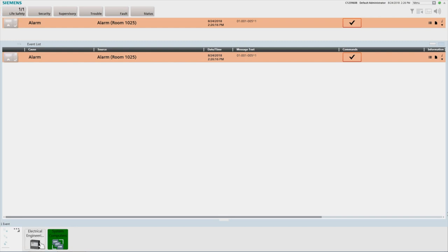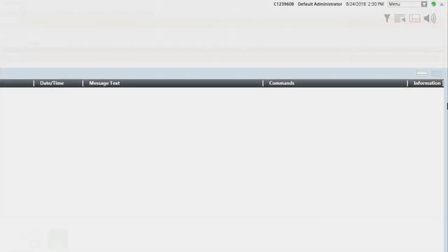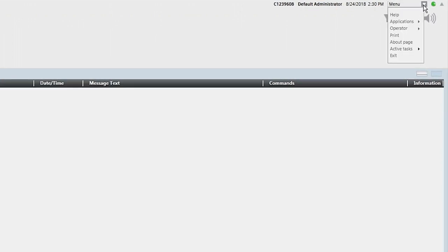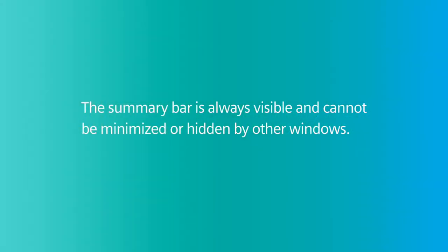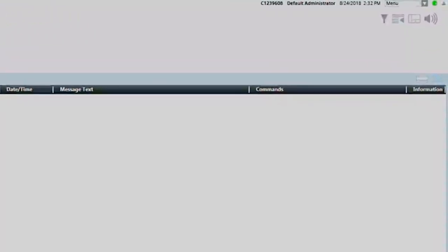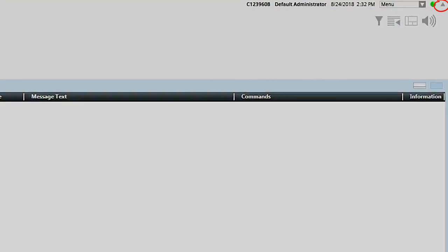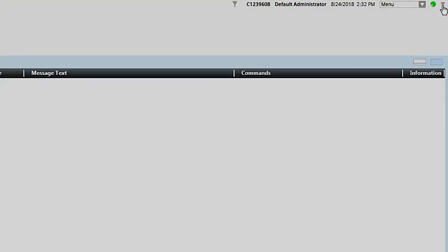In addition, the two most important events requiring attention are displayed in the event detail bar just below the event lamps. The summary bar also contains information such as who is logged in, the current time and date, and a menu to access the online help tool, switch operators, and more. When all connected panels are in normal standby mode, the summary bar will indicate 0 of 0 in each event lamp, and no events will be displayed in the event detail bar. Note that the summary bar is always visible and cannot be minimized or hidden by other windows. However, it is possible to collapse the summary bar by clicking on the upward pointing triangle in the far upper right-hand corner.